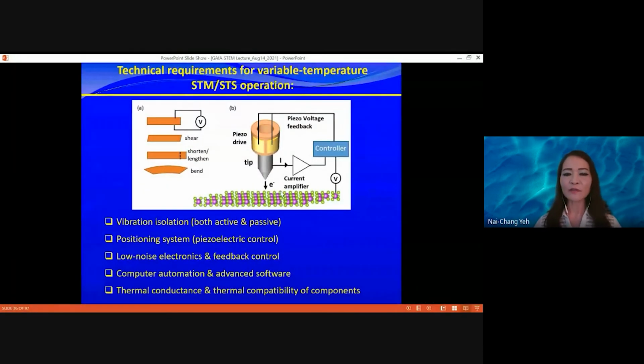But to do it right, if you have such a sensitive system, you must make sure you have very good vibration isolation, and you must have a very good positioning system. Also, you have to make sure you have low noise electronic systems, and you need computer automation because you're going to acquire so much data, requiring good software to control and analyze it. Also, if you want to go to low temperatures, you have to make sure all of your components have comparable thermal properties. Otherwise, if your thermal contraction and expansion coefficients are different for your different components, the system will fail when it goes to low temperatures. So those are the things you need to know.